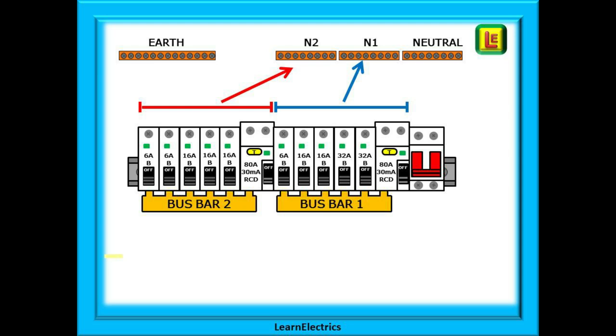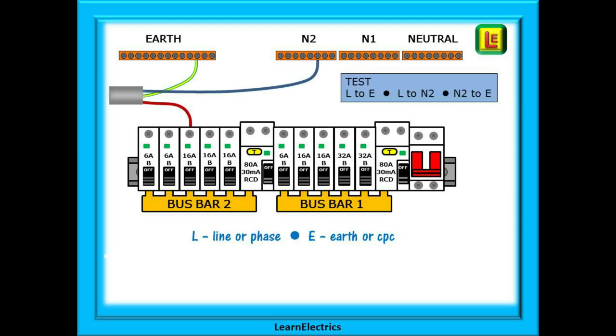A dangerous and potentially very embarrassing situation. The insulation resistance test is nothing more than testing between all possible permutations for the three conductors, which gives three tests: line to earth, line to neutral, and neutral to earth. If you cannot be certain that the light switches are in the on position, then you must change the position for each luminaire and retest the circuit. This ensures that all the wiring has been tested. Be aware that with two-way switching or intermediate switching, you must operate only one switch of that circuit — any switch, it doesn't matter, but only one.